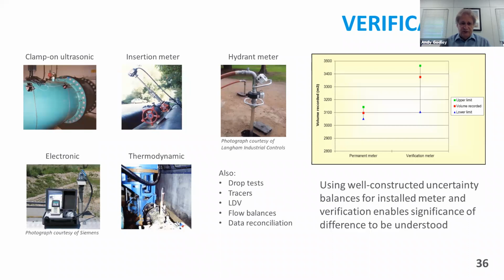And the logical consequence of that is that if the electronics are performing correctly, then the meter is still measuring correctly. There's a couple of caveats around that, particularly around hydraulic disturbances. The meter may still be performing and measuring electronically well, but if you've got a poor velocity profile in there, there may be effects from the hydraulics that electronic verification will not be picking up.